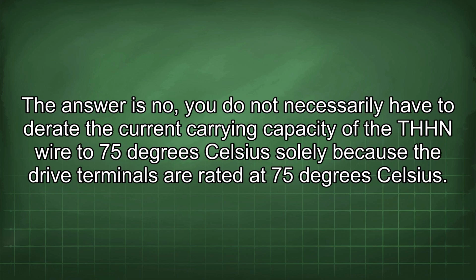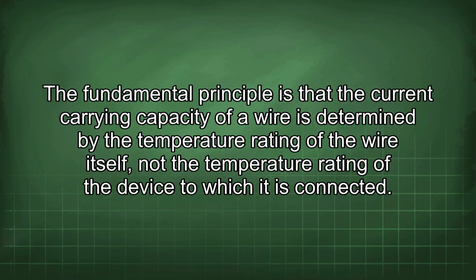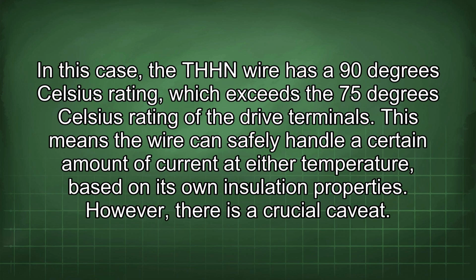The answer is no. You do not necessarily have to derate the current carrying capacity of the THHN wire to 75 degrees Celsius solely because the drive terminals are rated at 75 degrees Celsius. The fundamental principle is that the current carrying capacity of a wire is determined by the temperature rating of the wire itself, not the temperature rating of the device to which it is connected. In this case, the THHN wire has a 90 degrees Celsius rating, which exceeds the 75 degrees Celsius rating of the drive terminals. This means the wire can safely handle a certain amount of current at either temperature based on its own insulation properties. However, there is a crucial caveat.